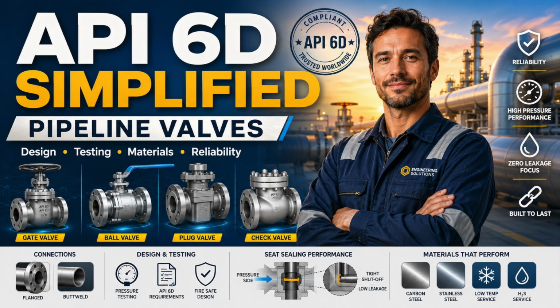Three words do not define the hazard. You need to define what you are trying to achieve: operational isolation, maintenance isolation, leak detection, product segregation, emergency isolation. Do you require two seating barriers? Do you require independent verification? Can one failed seat be tolerated? Can the cavity be vented? Can trapped pressure occur? Can maintenance personnel safely rely on the arrangement? Only after those questions are answered should you select the hardware. A single valve with two seats is not automatically equivalent to two independent valves with a bleed between them.